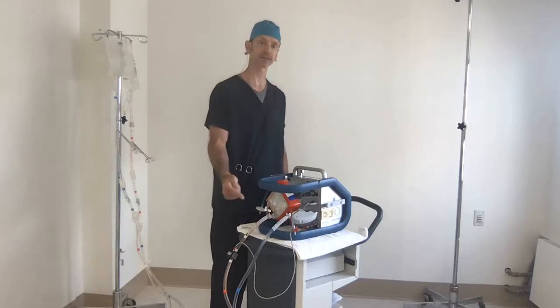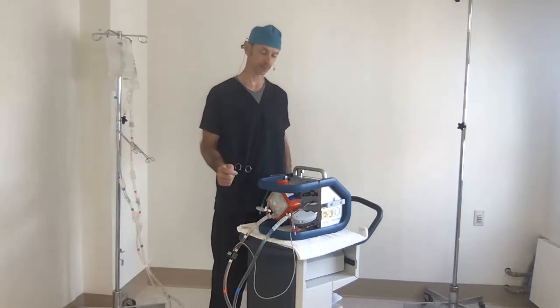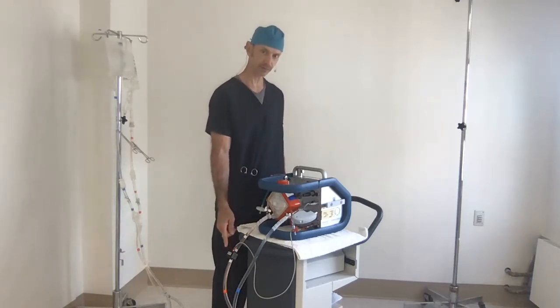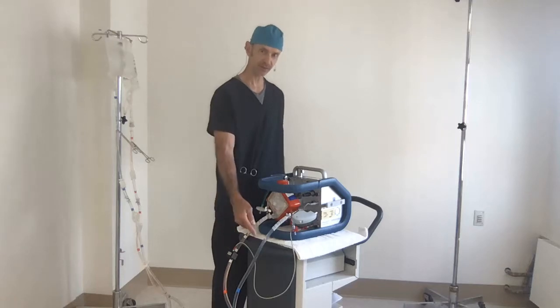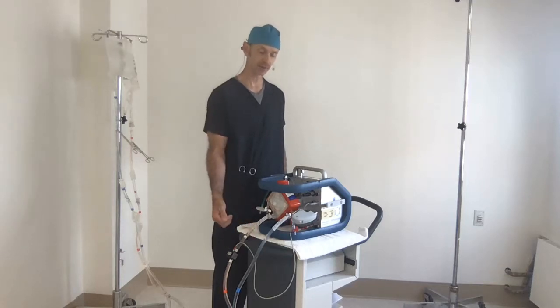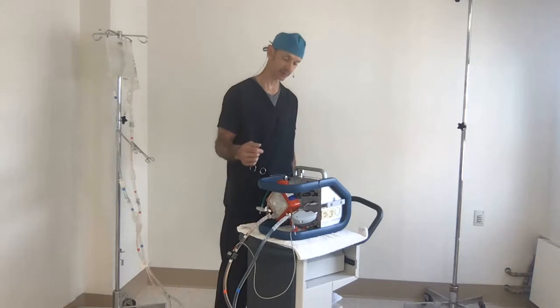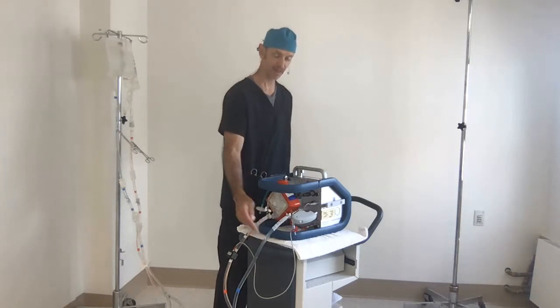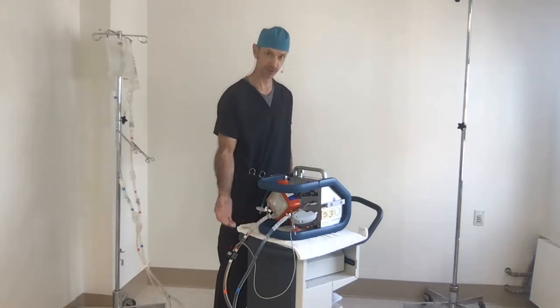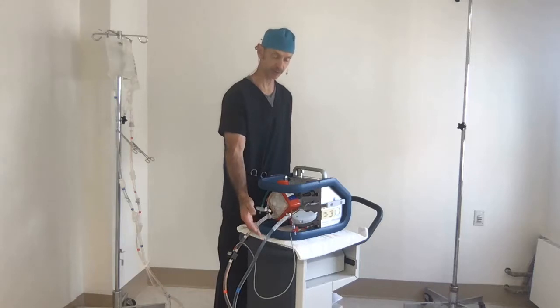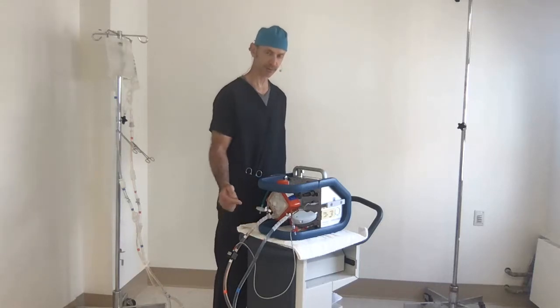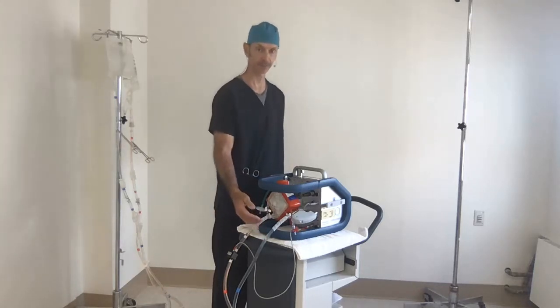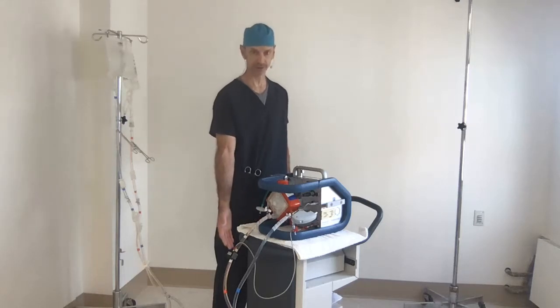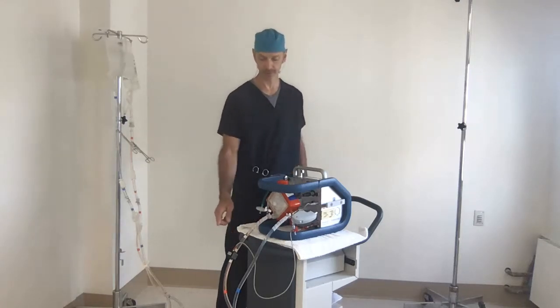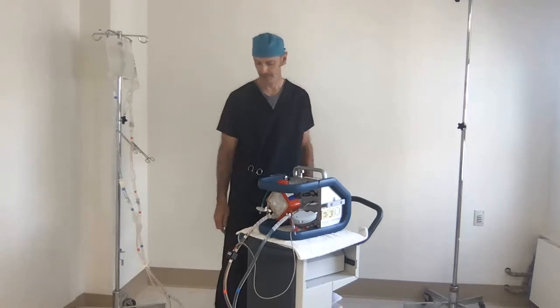Don't ever put that on the venous line. Very important, because this is a flow and bubble detector. And even though it fits on the venous side, it has a different intervention than the venous bubble detector. So you don't want that intervention to happen for venous air. You want the intervention you're going to set to happen for arterial air. So we'll only put this on the arterial side.